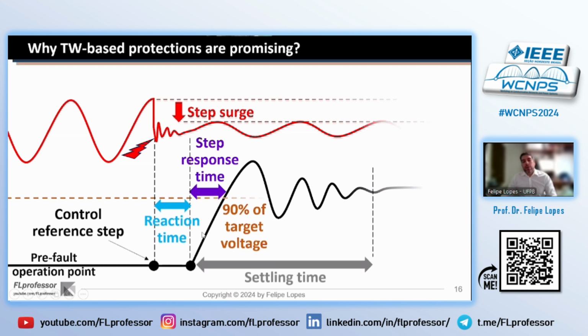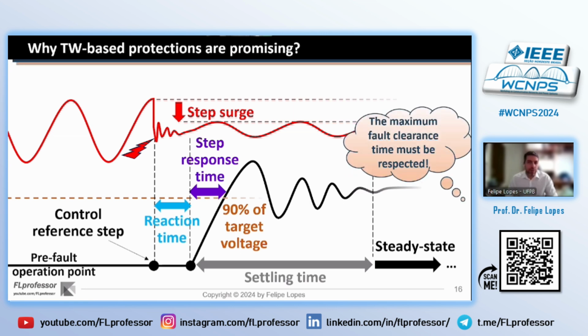And this is why a lot of people have reported that waiting a little bit of time to take decisions using conventional protections would be beneficial, because after the settling time, the system tends to enter the steady state. And by doing so, conventional protections could be reliably applied. But the problem is that there is a maximum fault clearance time that must be respected, such that limiting the time to take decisions here can make the application of conventional phasor-based protections very challenging.